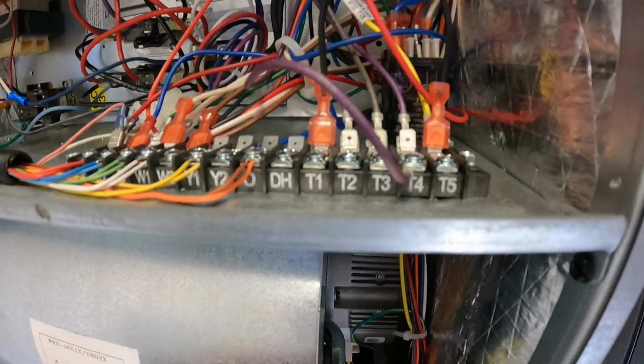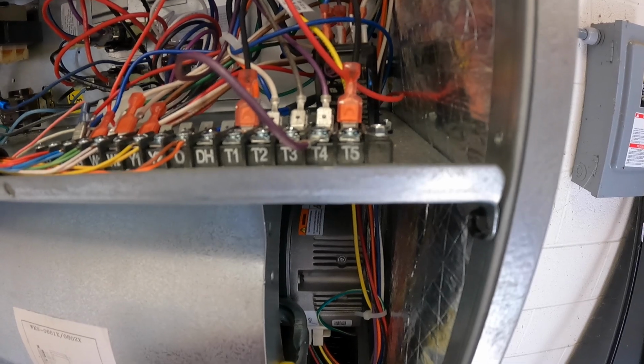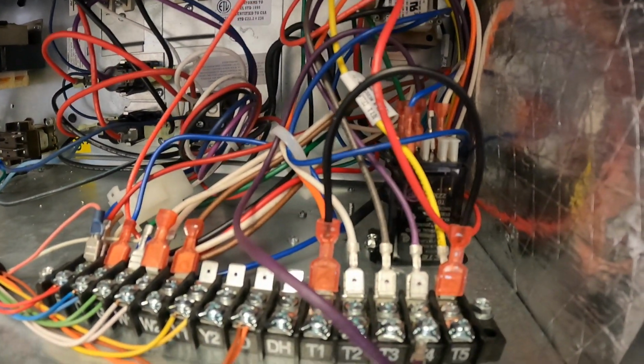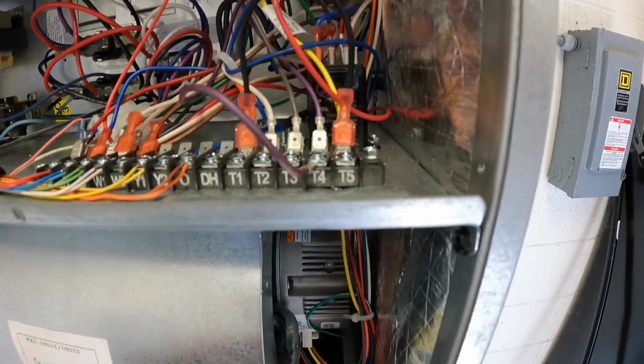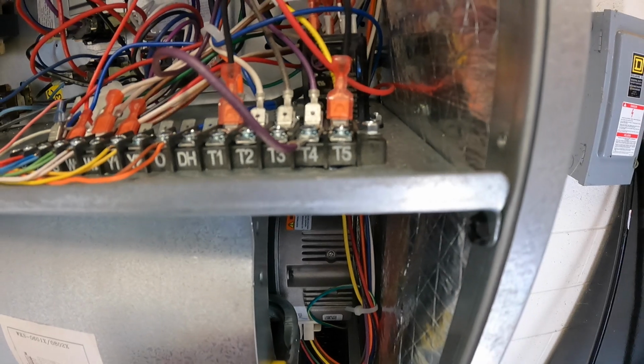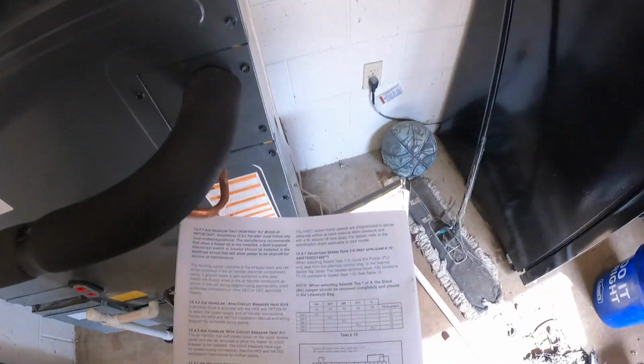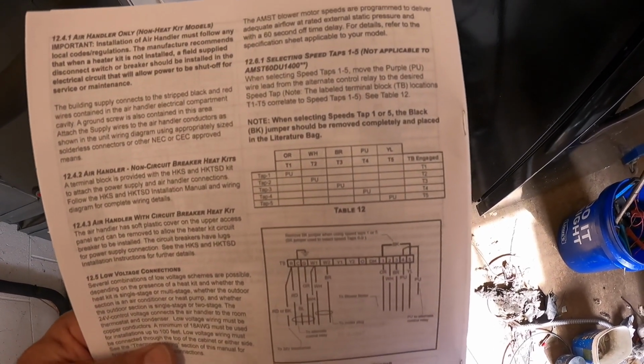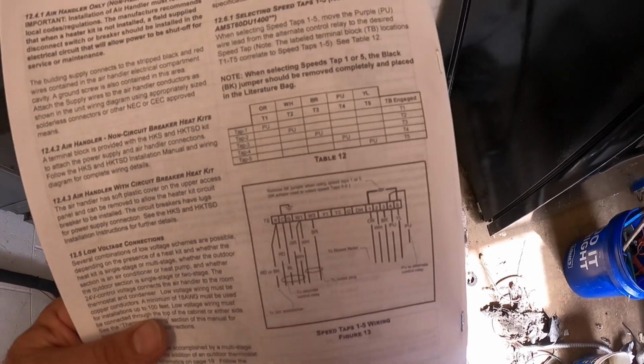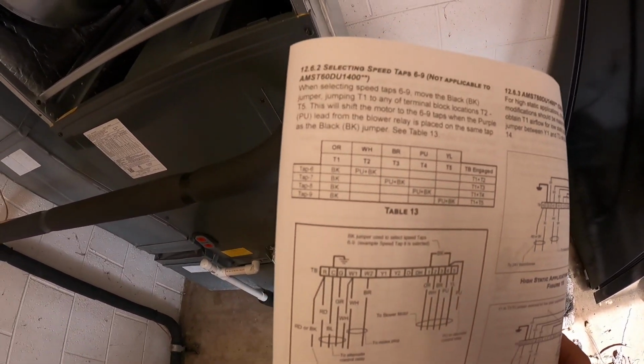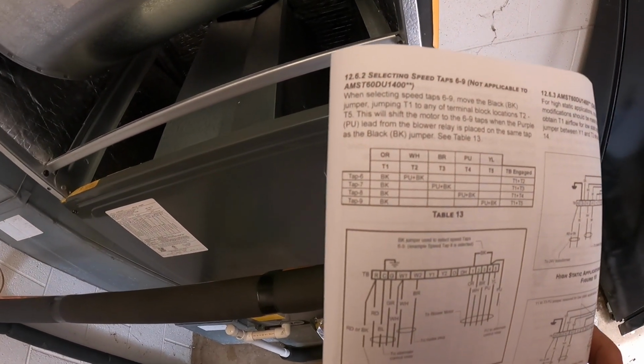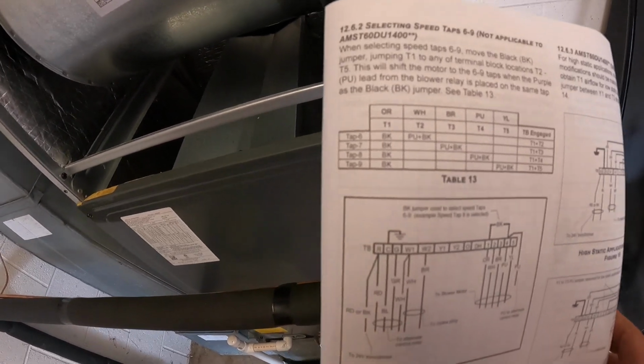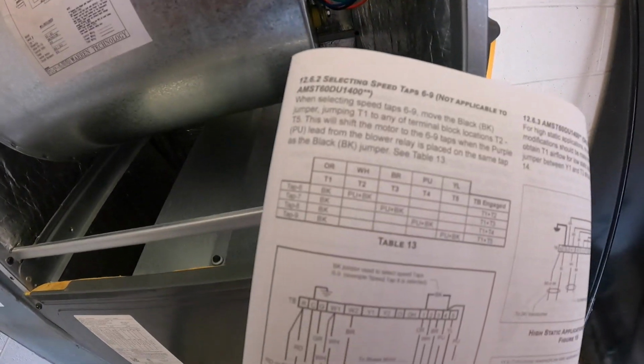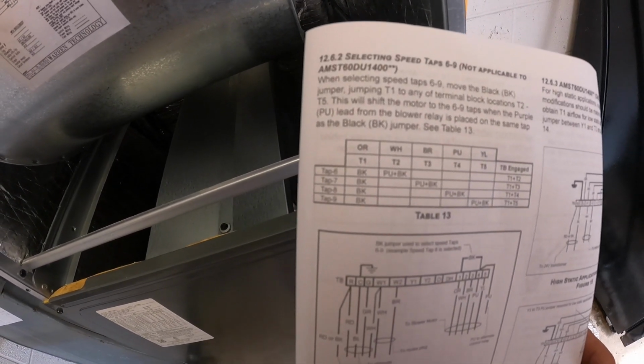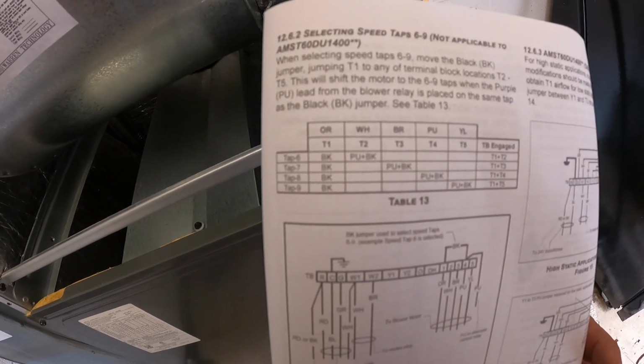Okay, here's our terminal strip, and you can see we're on T4. The reason we know we're on T4 and not some other speed is because there's a black jumper between T1 and T5. Now, if you were using T1 or T5, you're supposed to take that black jumper off completely, and it's all in the literature here. It's kind of confusing, but if you wanted to use T6, T7, T8 or T9, you have to run the black from T1 to T2, for instance, and then if you put your wire on T2, you wind up with T6. Or if you run your wire from T1 over to T3, you wind up with tap 7 if you put your purple on T3.